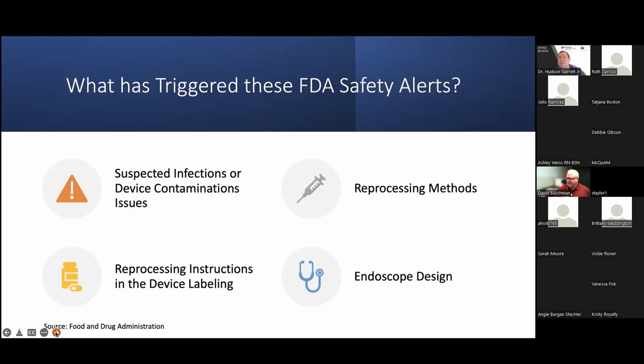The second piece is that there were a lot of issues identified with reprocessing instructions. We've just seen an example of this where there's a currently marketed product with FDA clearance that's used quite often across the United States, that even if you follow the manufacturer's instructions, it still fails reprocessing, which means that device is not safe to be used in patients.